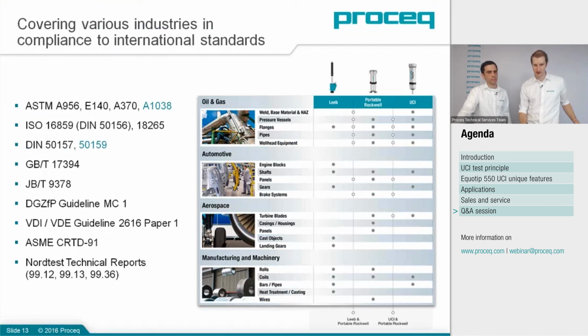Great, thanks Christoph. One additional quick note: ASTM E140 is a conversion standard which UCI utilizes for conversion, and ISO 18265 is also a conversion standard. So in the instrument, when doing the conversion application, you have the option of choosing between the two.